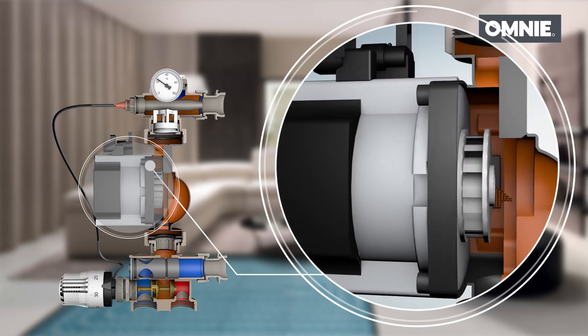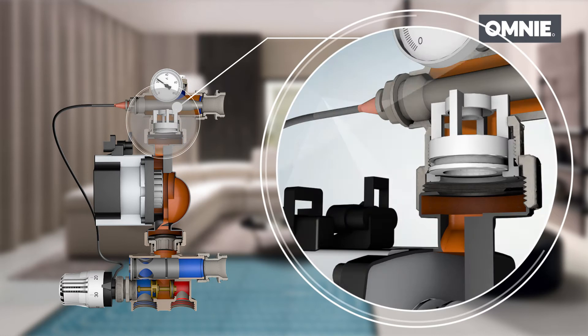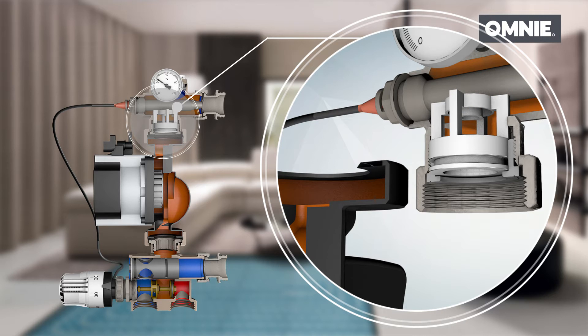The high efficiency pump. The check valve, positioned immediately downstream of the circulator, makes filling the system more simple, with the pre-installed drain fill valves located at the end of the manifolds. The same valve also reduces the escape of water should replacement of the pump be required in the future.